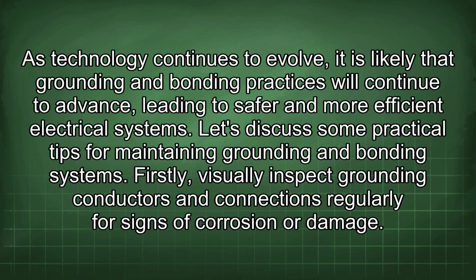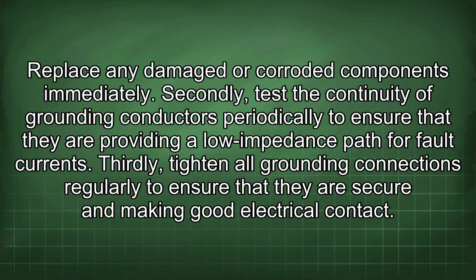Firstly, visually inspect grounding conductors and connections regularly for signs of corrosion or damage. Replace any damaged or corroded components immediately. Secondly, test the continuity of grounding conductors periodically to ensure that they are providing a low impedance path for fault currents. Thirdly, tighten all grounding connections regularly to ensure that they are secure and making good electrical contact.